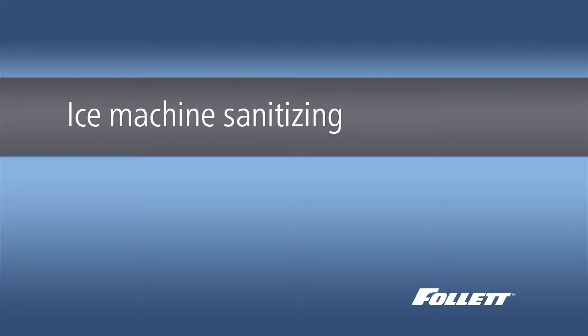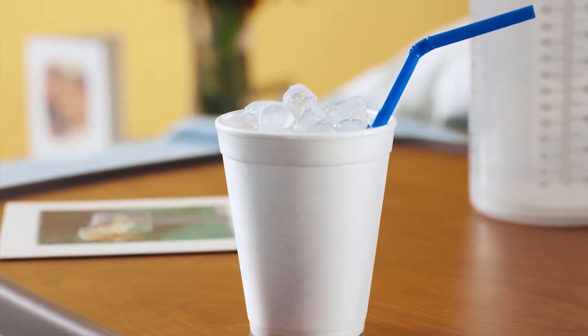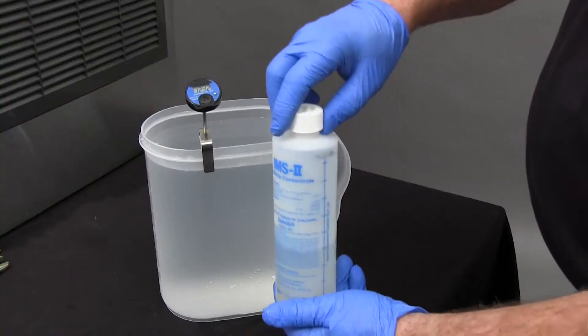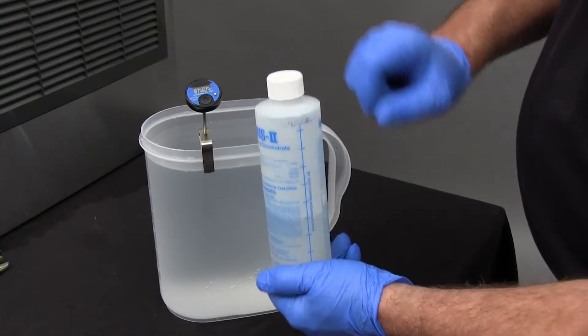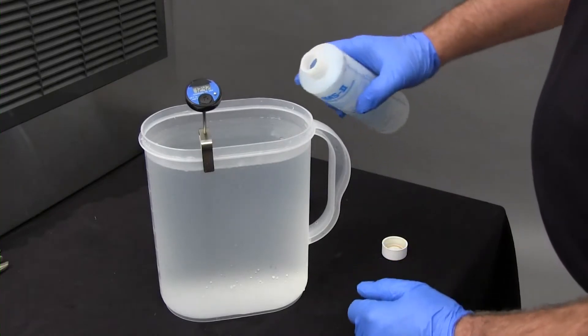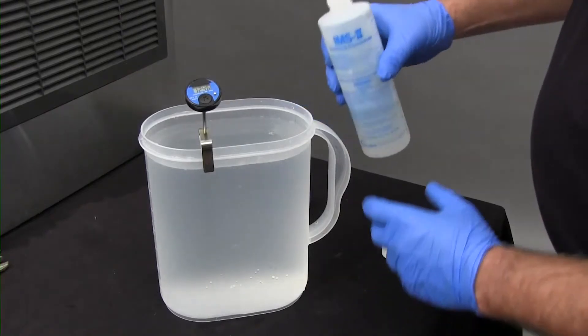Sanitizing is necessary to provide high-quality, sanitary ice. Sanitizing removes undesirable and potentially harmful microbial growth from the ice machine. Mix the sanitizing solutions per the manufacturer's instructions. Use 1.6 ounces of Nu-Calgon IMS-II sanitizer with 1 gallon of water that is at least 100 degrees Fahrenheit. The remaining steps to sanitize the ice machine are the same as the steps used to clean the ice machine. Simply repeat the process using the sanitizing solution in place of the cleaning solution.